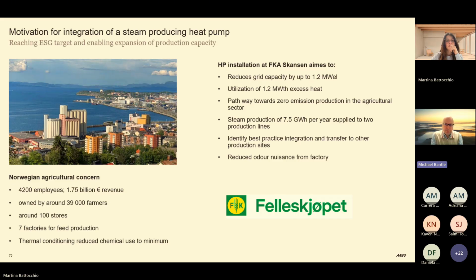And this pilot project was also the first one where we actually integrated this technology into this type of process. So it was also the aim and target to identify the best practice integration principles and operability for this kind of system, so we can roll it out to several factories as well. Last but not least, this was an aspect that we also discovered with our heat recovery unit. We are basically taking out sensible as well as latent heat. That basically means moisture, which we are condensing out, and by doing so, we also remove a certain amount of odor from the factory exhaust, which was there before.